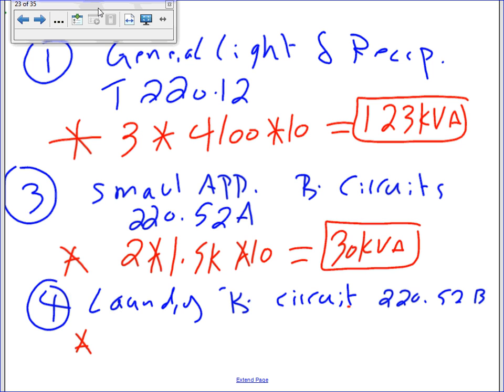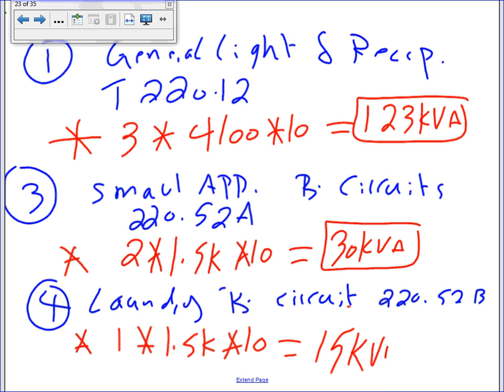Okay. That's your small appliance circuits. My friends, laundry: each one of them is going to have a circuit allocated to laundry. The laundry is allocated 1.5 kVA each, and there are 10 of them. 220.52(B) tells you this. And that will get you 15 kVA for this apartment building. 15 kVA. Straightforward, guys. Directly from the NEC code book. No gimmicks, nothing.